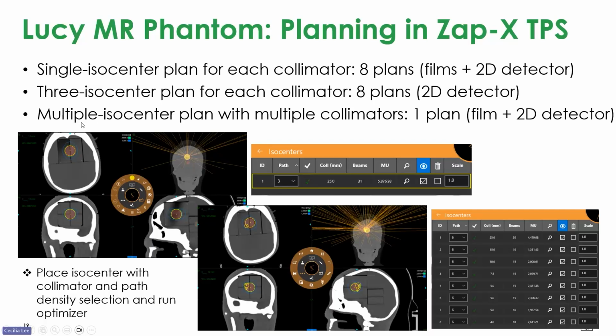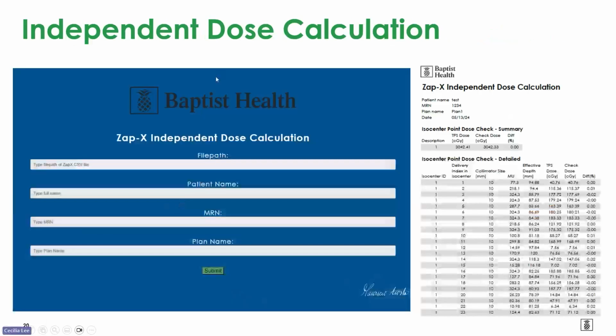And then I created a multiple isocenter plan with multiple collimators. That means I have multiple isocenters, but using different collimator sizes. And then I delivered using film and a 2D detector. Then for each plan I ran an independent dose calculation. We created our in-house, web-based tool, so we can run it quickly. It takes less than a minute, and then creates a QA report.